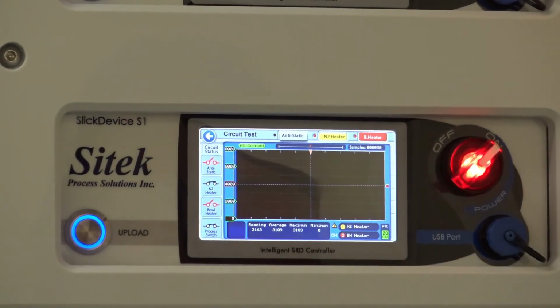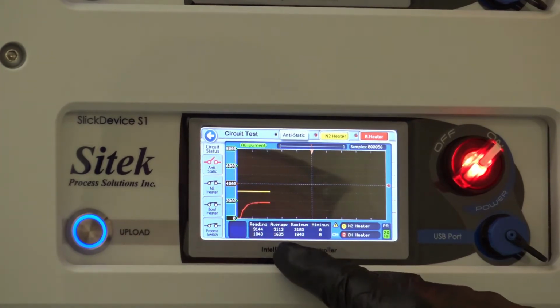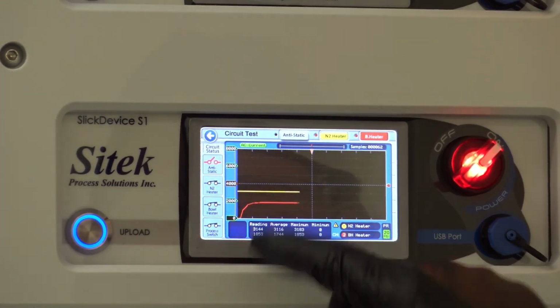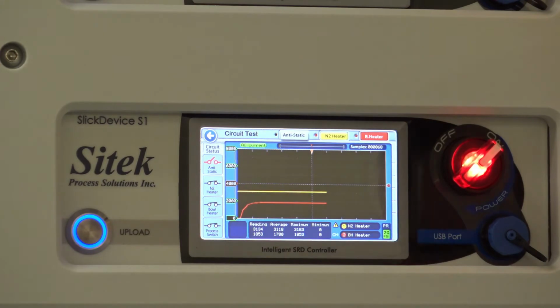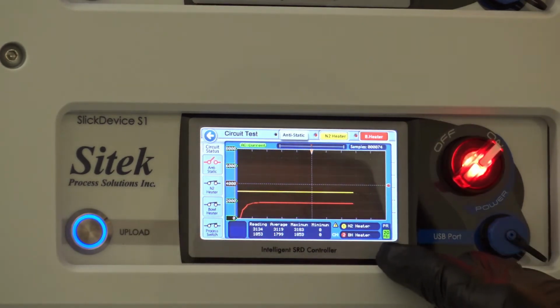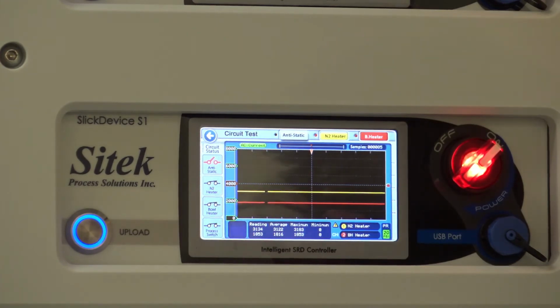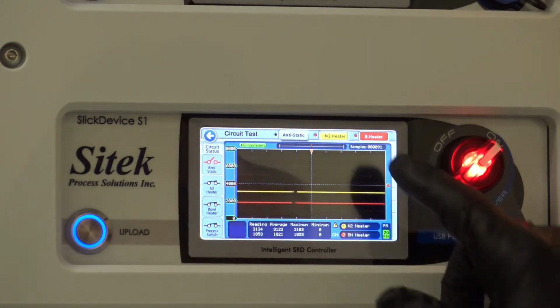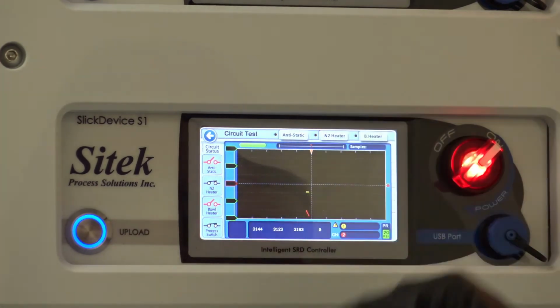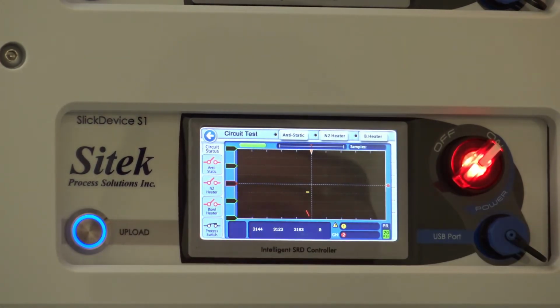I can also check the bowl heater. Okay, the bowl heater is red. The N2 heater is yellow. It uses a different amount of power, but you can see they're both running and they're both consuming the needed power, and they're not failing. A very easy test for maintenance people to do PMs on a monthly basis to make sure the parts are working correctly. I'll turn those off. Okay, so as you can see, it's a great thing.